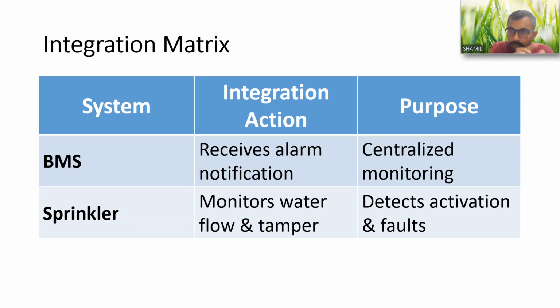Next to the flow switch and the tamper switch, there will be a monitor module, which is connected to the fire alarm control panel. The main purpose of the monitor module is to interact with the flow switch and the tamper switch. So it basically detects the activation and faults. So this is how a sprinkler system communicates with the fire alarm system.